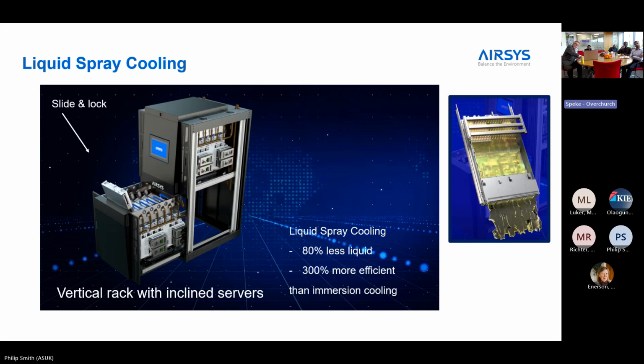So if I go through to there we go. So what we do is we're spraying the server with the dielectric liquid. It runs over the CPU, drains down into the bottom of the unit. So they're not immersed. We've actually only got about that much of liquid in the bottom of the drawer. The drawer pulls out. You've got 7 2U servers, 7 in the top, 7 in the bottom, 14 in total. You can reject 50 kilowatts or so of IT load within that one cabinet, which is sort of the same size as a rack within a computer room.